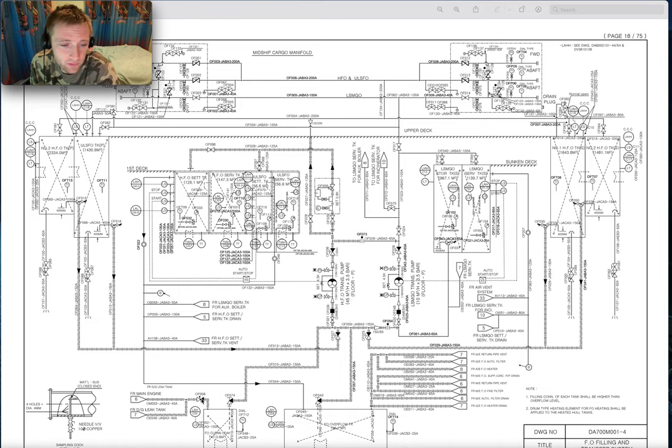In many vessels there is not this kind of tanks. Everything from an engine and from diesel generator leakages goes here, but here they have separated, so it will be easier to identify this kind of leakages. Most of the leakages that were coming from diesel generator were not detected in the previous vessels. It was really difficult to detect, because some of this diesel generator leakage was going to the oily bilge tank, and as we know, the oily bilge tank was about 30 to 40 cubics, depending also on the vessel size, and it was really difficult to identify.